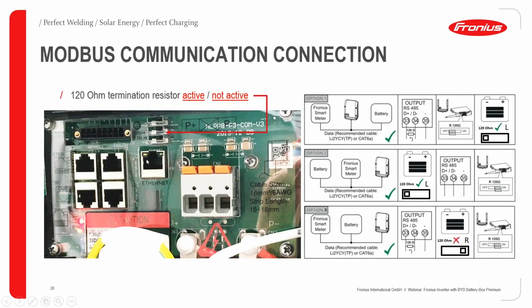As mentioned before with your Modbus, this is what the connection area looks like. These little dip switches - you want all of them facing left to have the 120 ohm resistor on. Depending on which option you want, inverter in the middle, smart meter in the middle, or battery in the middle, that determines if this is on or off. In this case, it's the middle one.